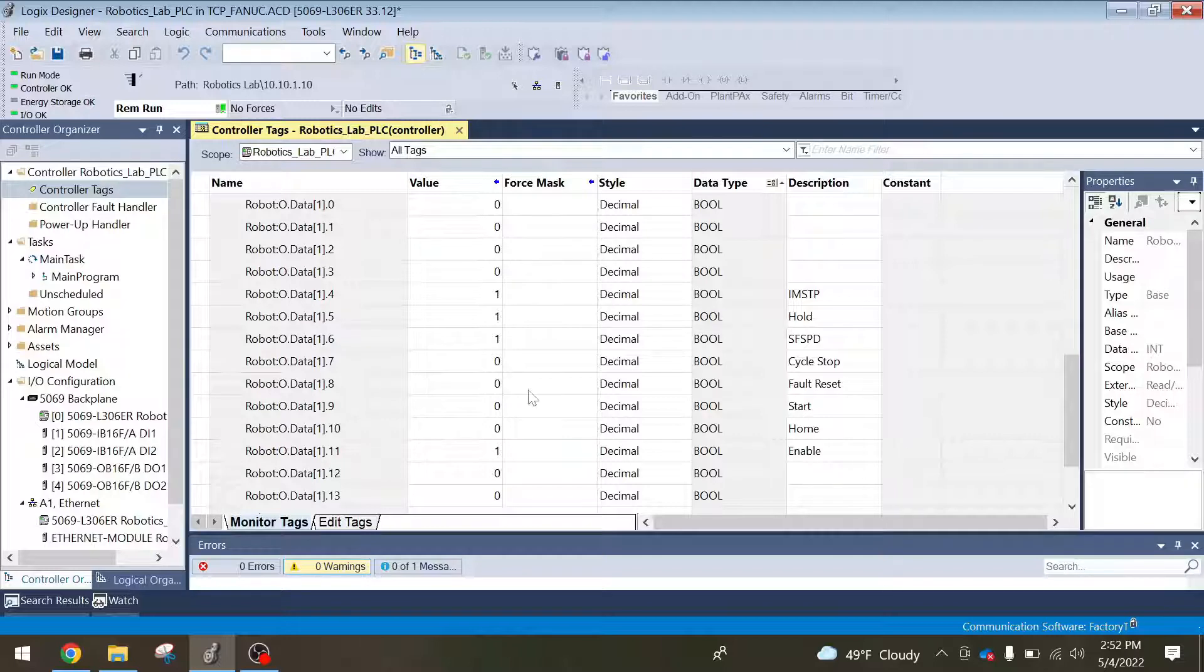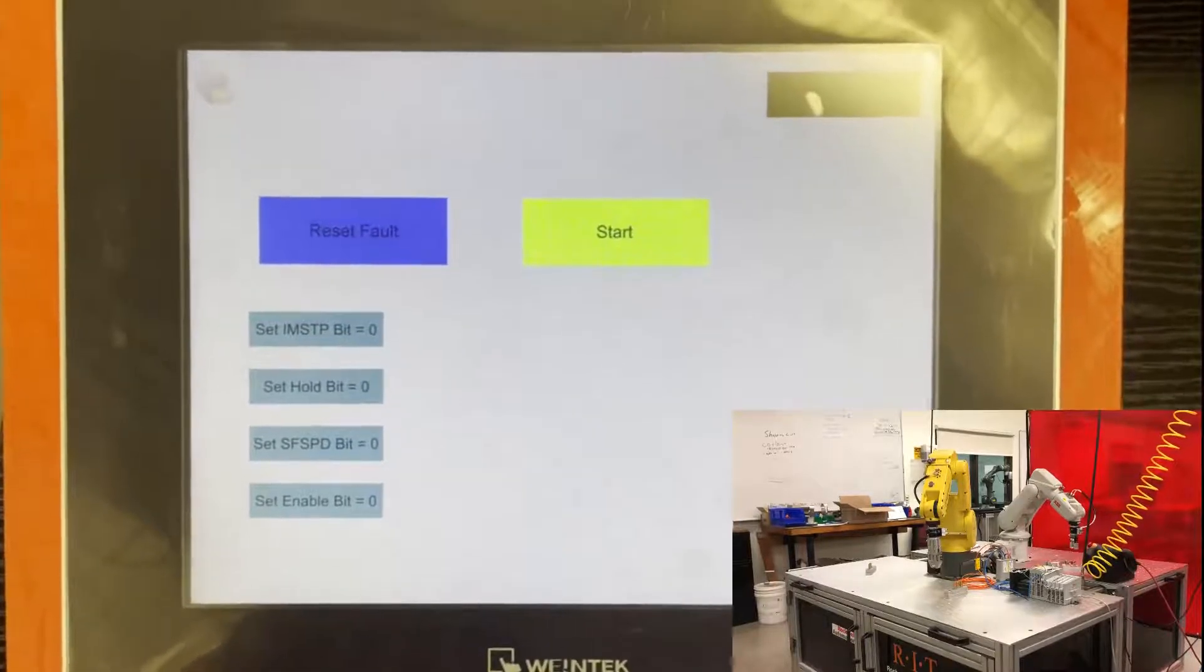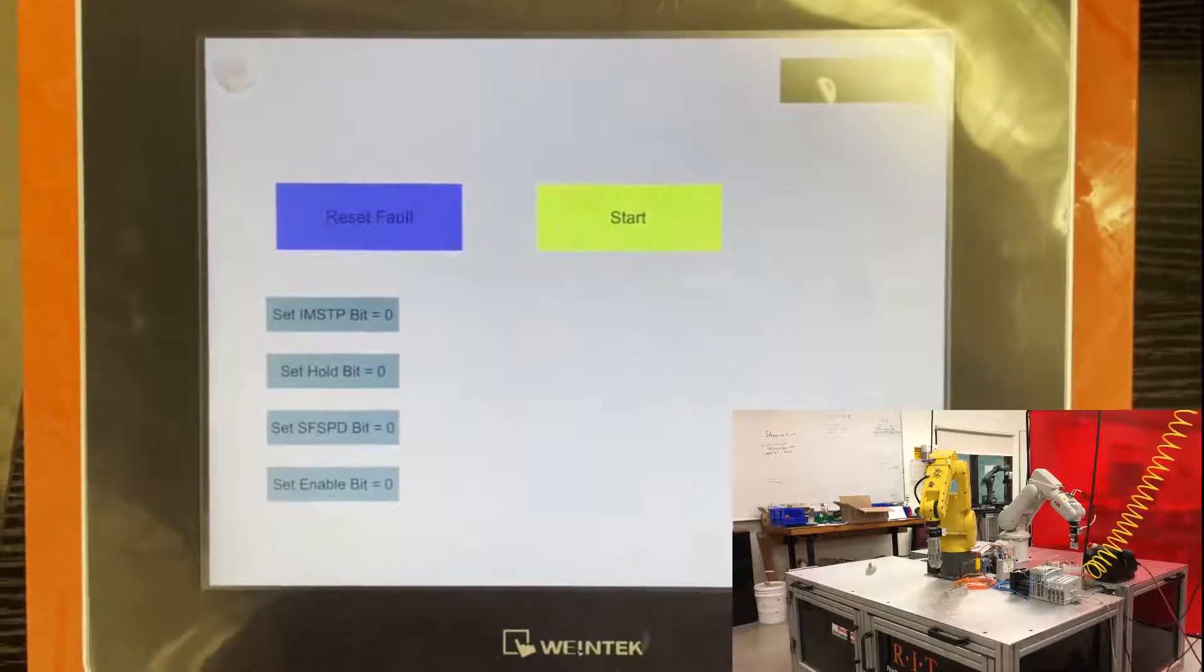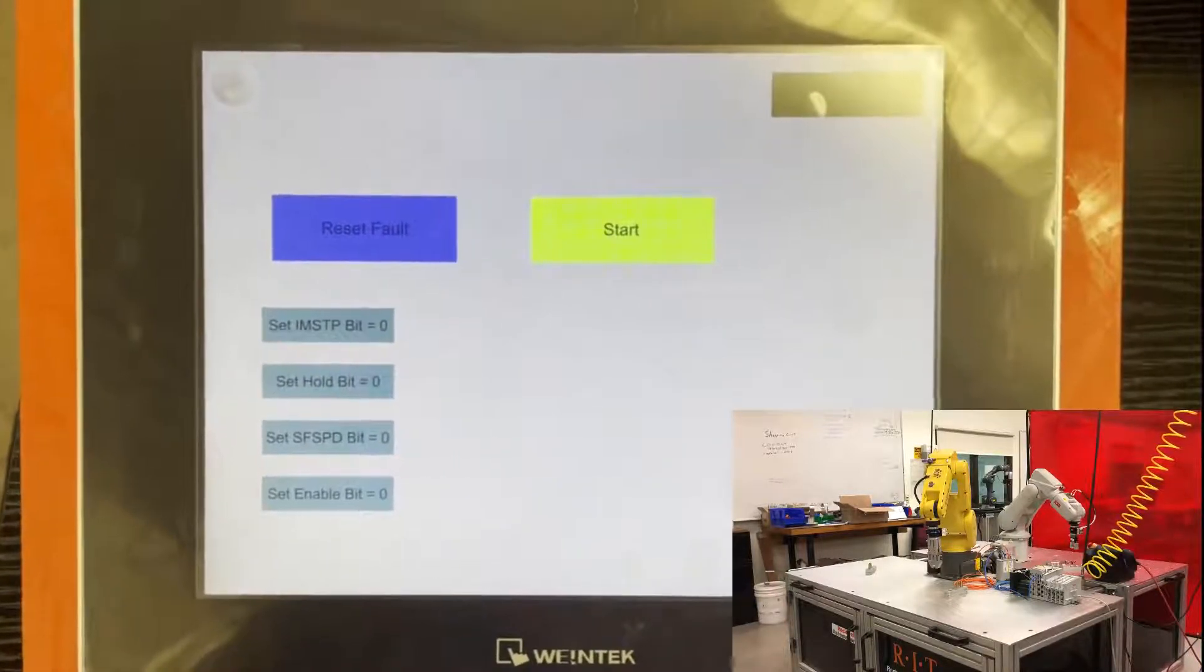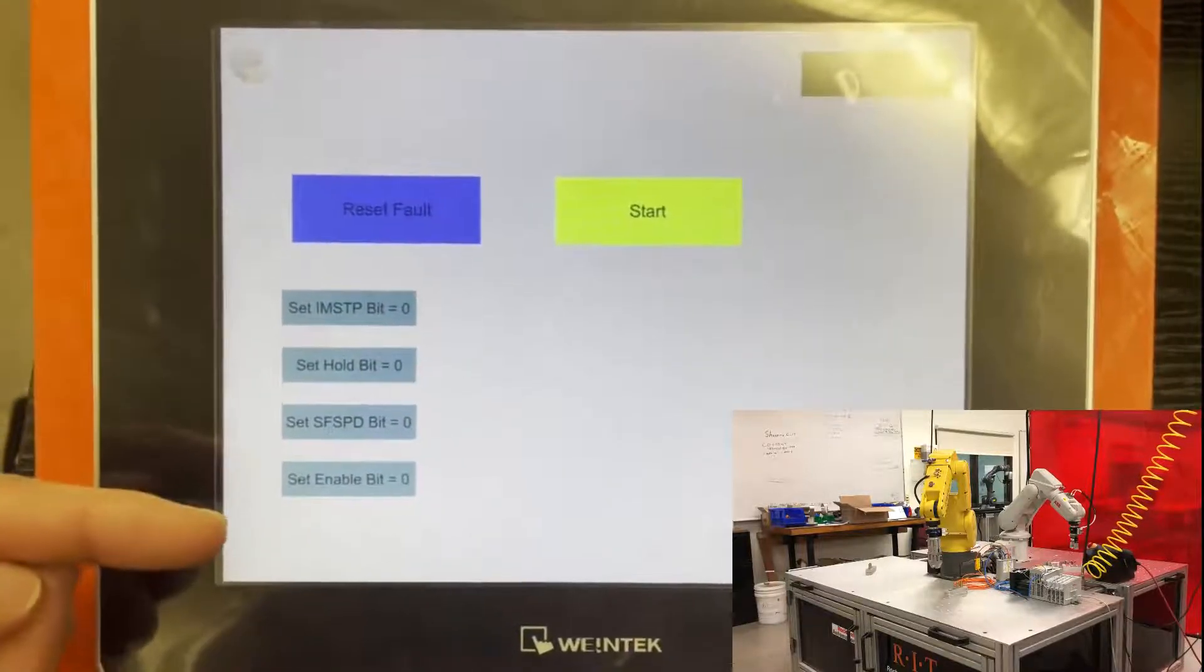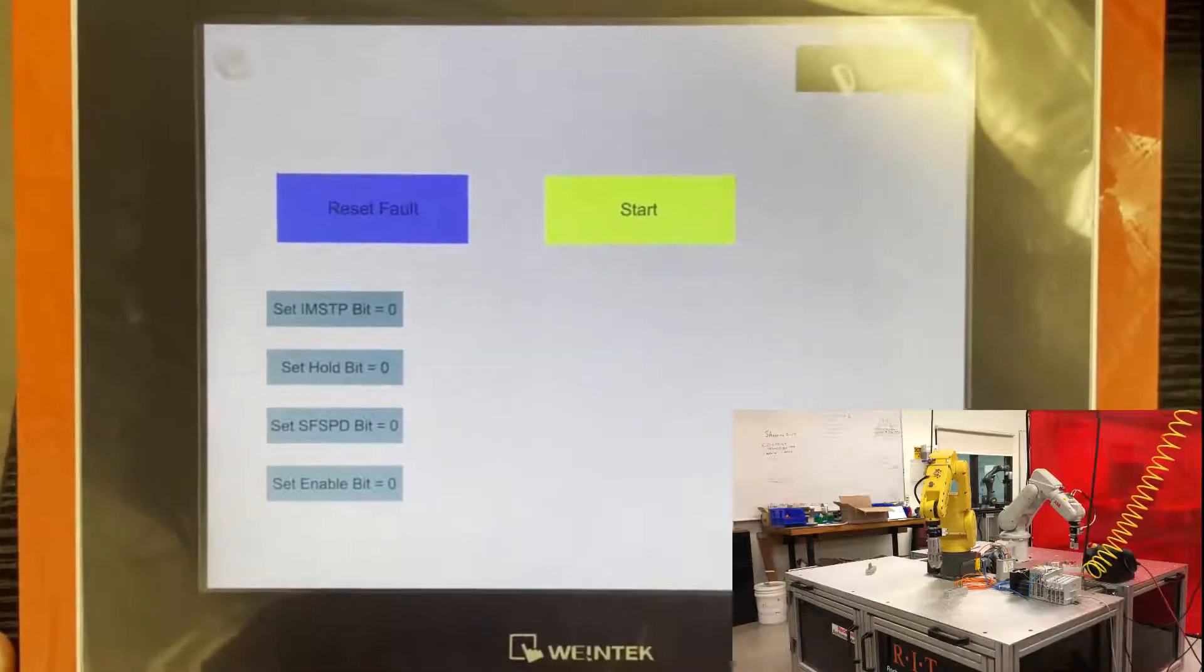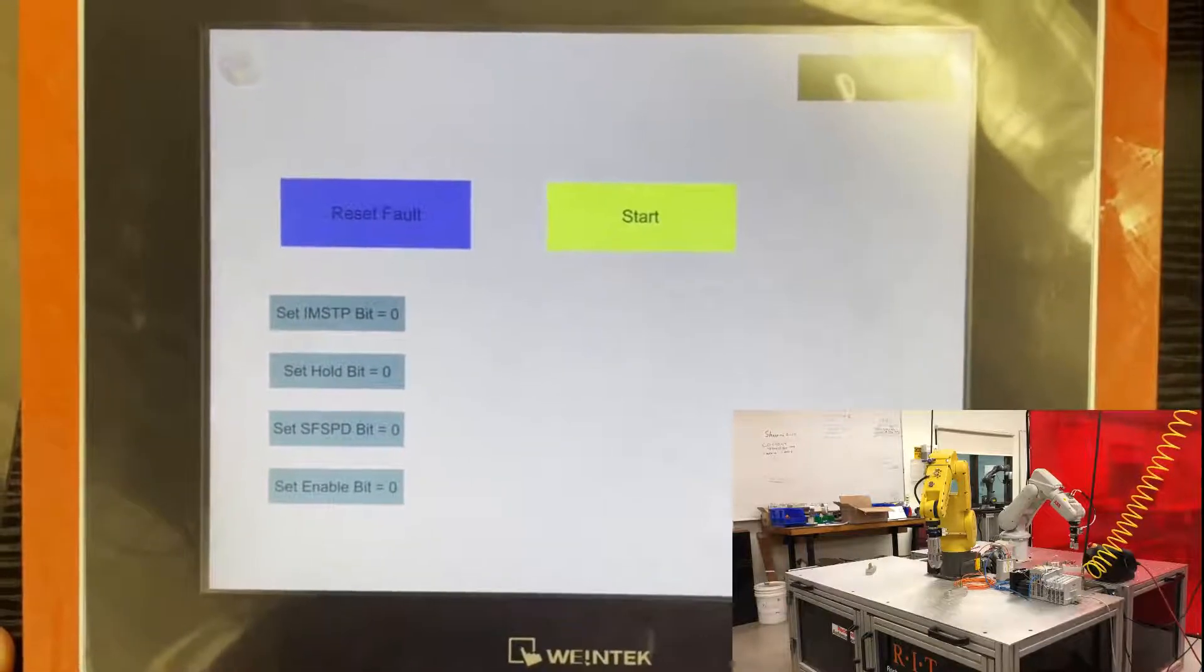In this section, I just want to show a simple HMI screen that I made to help show what each of the UOP signals does and what needs to be enabled in order for the robot to start. So as you can see here, these four bits here show the four bits that need to be enabled as outputs to the PLC or inputs to the robot for the robot to be able to start.